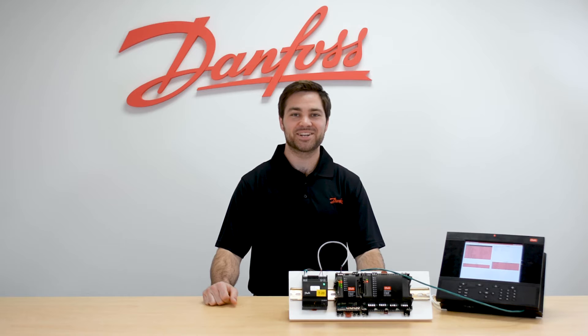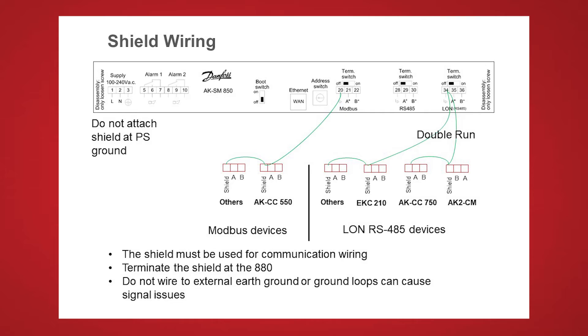The next thing to check for is your shield wiring on your communication loop. As you can see on your screen, the shield needs to be wired across each node and this needs to only be terminated at your 800 system manager. If you terminate this to an external ground somewhere else in the loop, you can create ground voltage, and that will not be good for your communication loop.